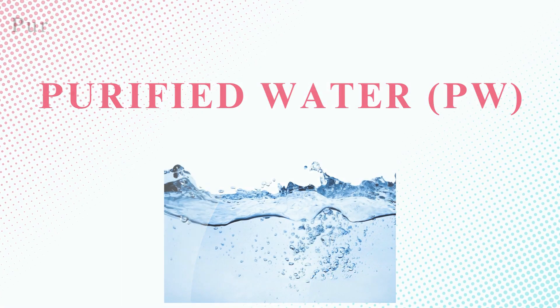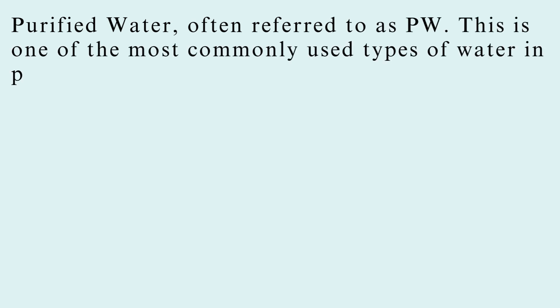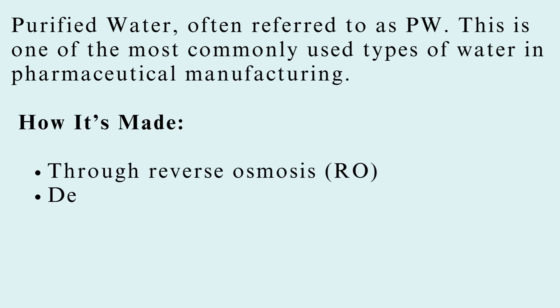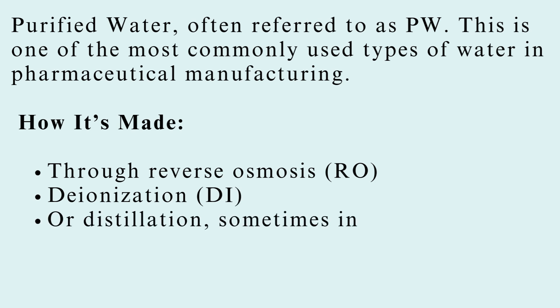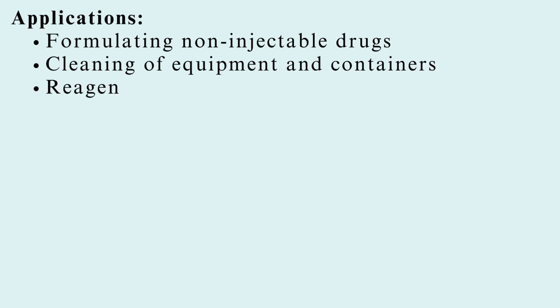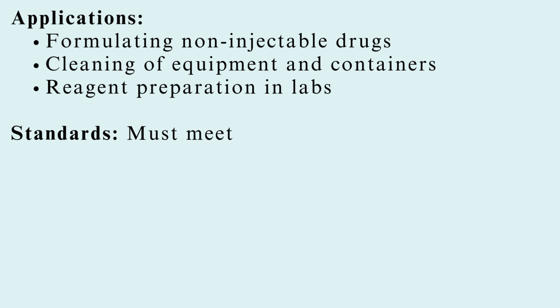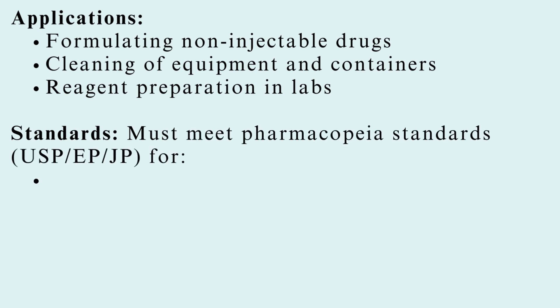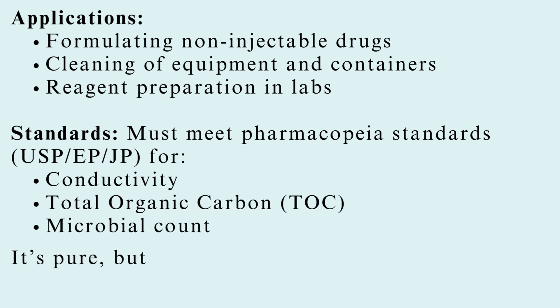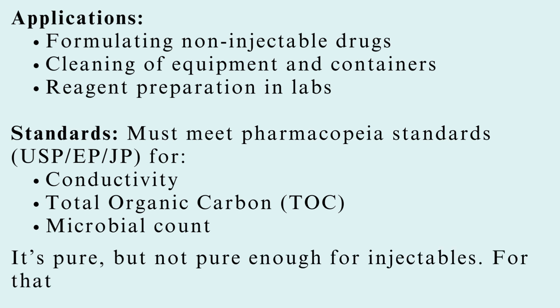Purified water, often referred to as PW, is one of the most commonly used types of water in pharmaceutical manufacturing. It's made through reverse osmosis, deionization, or distillation — sometimes in combination. Applications include formulating non-injectable drugs, cleaning of equipment and containers, and reagent preparation in labs. It must meet pharmacopoeia standards — USP, EP, JP — for conductivity, total organic carbon (TOC), and microbial count. It's pure, but not pure enough for injectables. For that, we need something more potent.